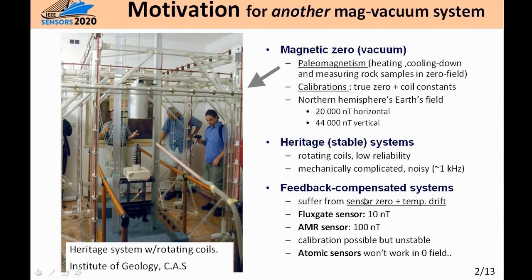Of course, there are systems which are already operated - I call them heritage systems. They are quite stable, using rotating coils, but because it's really mechanical and the coils have to rotate at quite high speed, they are really noisy at 1 kHz. Moreover, because it's based on Faraday's induction law, the voltages are very small, so it's also very susceptible to noise in the baseband. Any EMI appearing from 0 to 1 kHz would be induced in your coils and would interfere with your measurement.